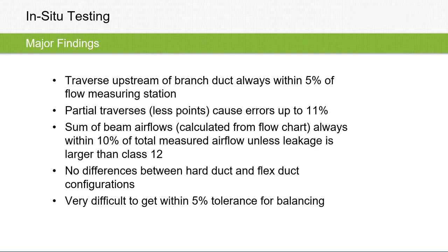We also, in our case, found no differences between hard duct and flex duct. I also think this is probably not a great conclusion for the field, just because we installed fresh flex duct. We're very careful with it. Nobody's poking holes in it to measure a traverse and not plugging that. In the field, you may have somebody bumping it. There could be some holes that form, maybe even fatigue just from moving it around a lot. So there could be some issues on site that we wouldn't have seen in our lab because we're very careful with the lab. Whereas on site, things can happen.